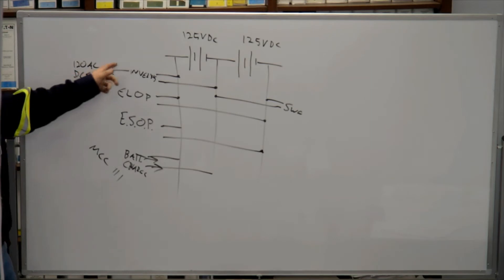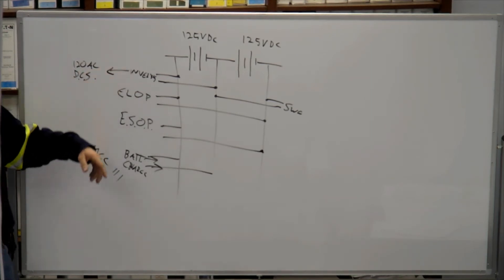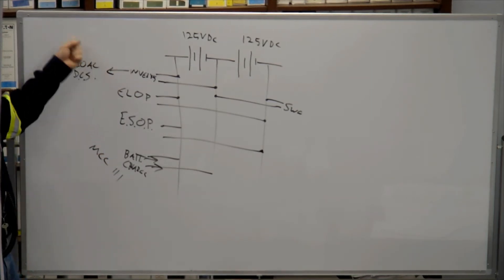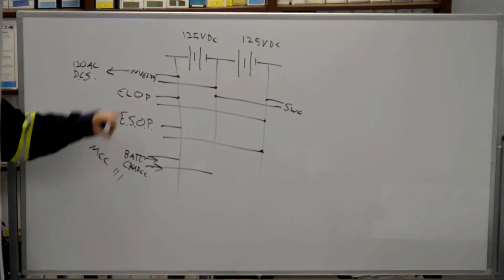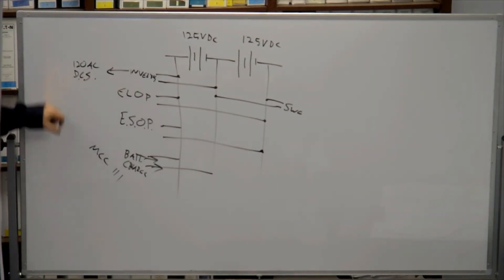And there's also a bypass for the inverters. So the inverters have 480 going to them so that you have a switch that you can just say no battery, but we still want to run all the 120 volt AC loads.